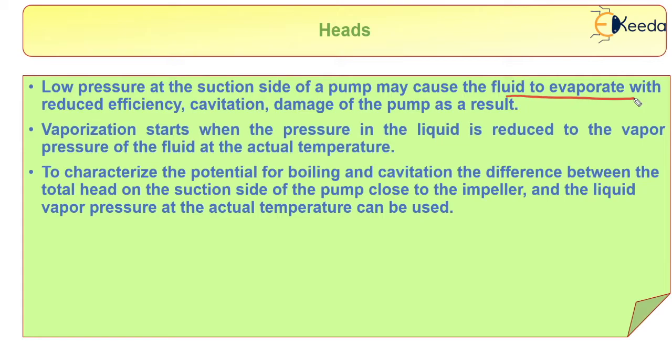Vaporization starts when the pressure in the liquid is reduced to the vapor pressure of the fluid at actual temperature. To characterize the potential for boiling and cavitation, the difference between the total head on the suction side of the pump close to the impeller and the liquid vapor pressure at the actual temperature can be used.